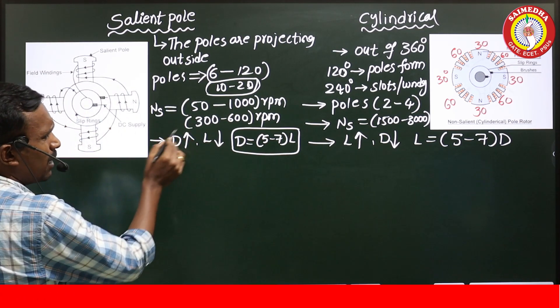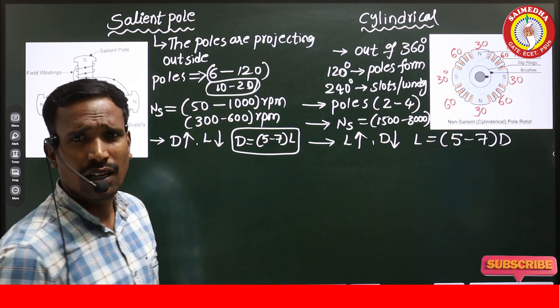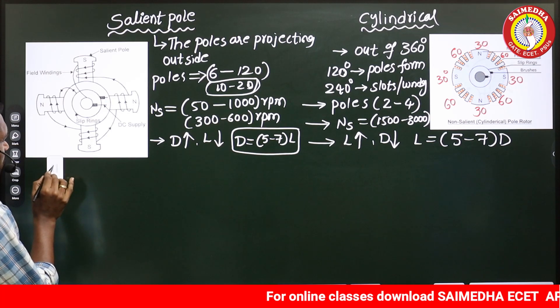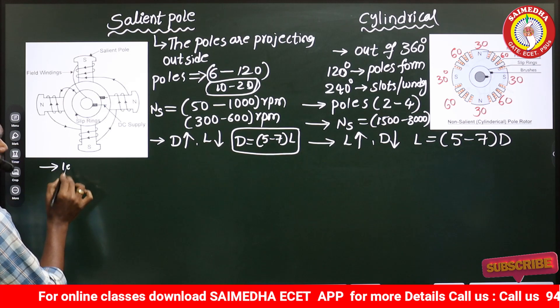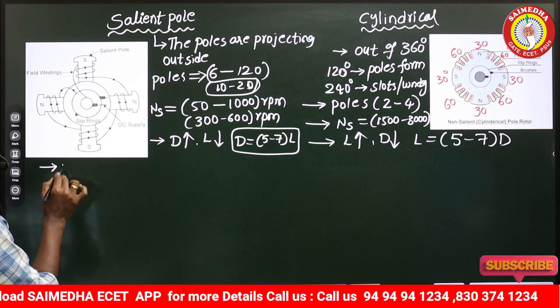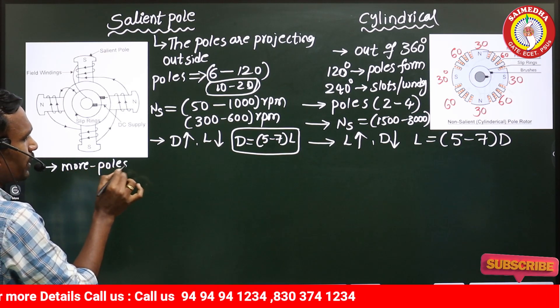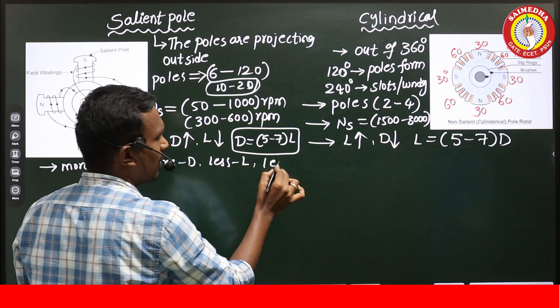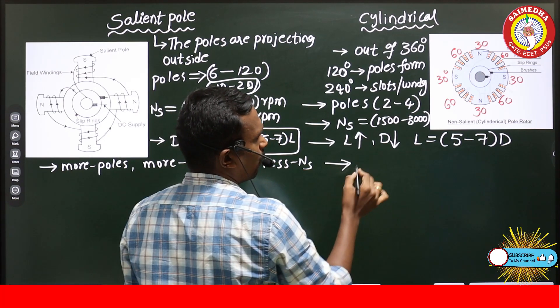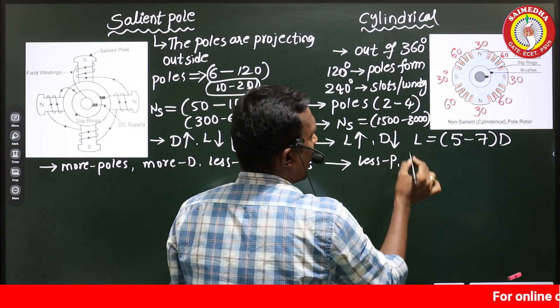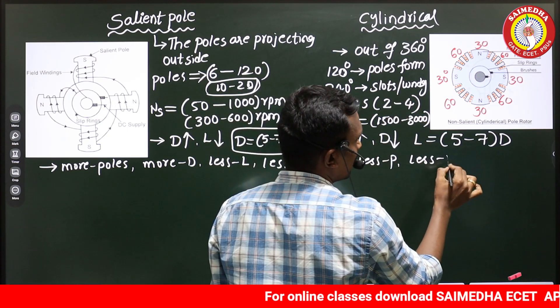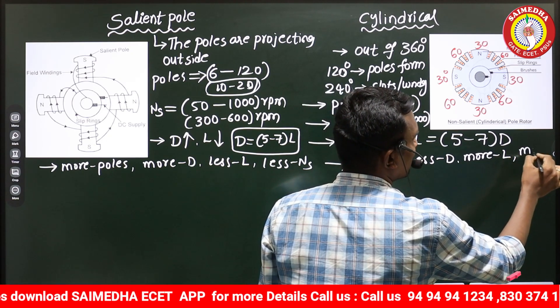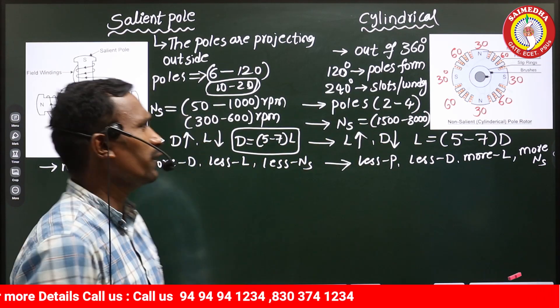When the diameter is more, the speed of the machine reduces; when the diameter is less, the speed increases. So for the salient pole: more number of poles, more diameter, less axial length, and less speed. For the cylindrical type: less number of poles, less diameter, more axial length, and more speed.